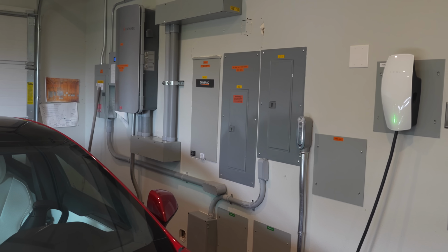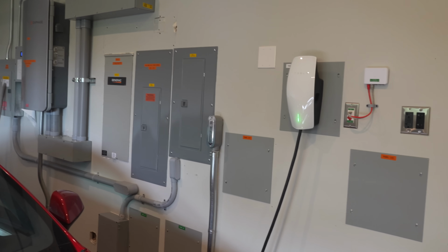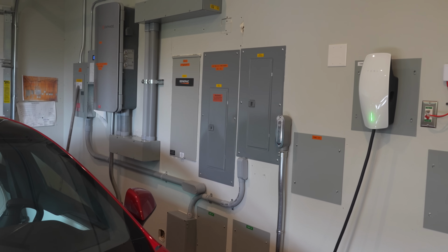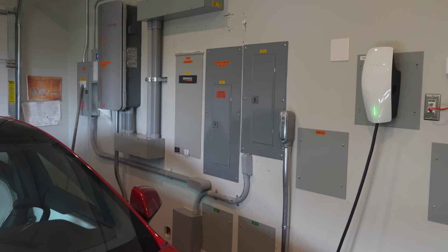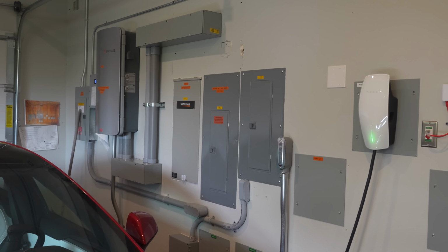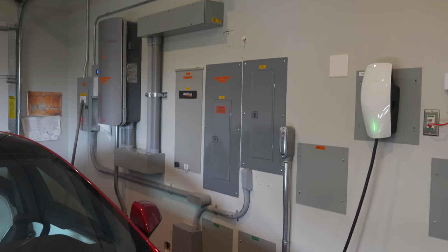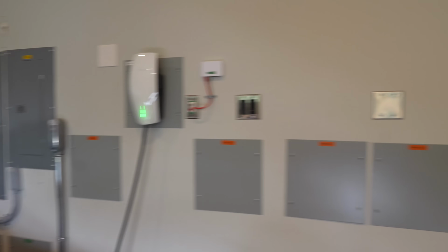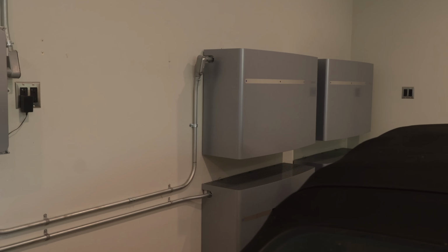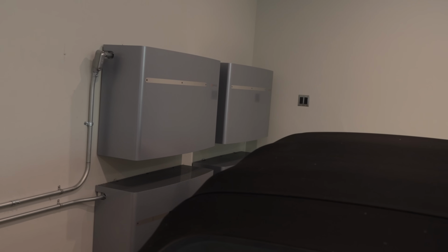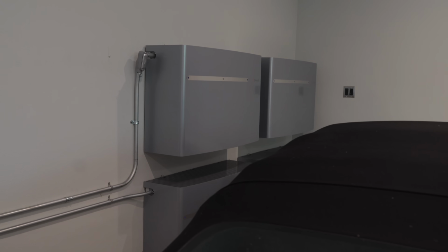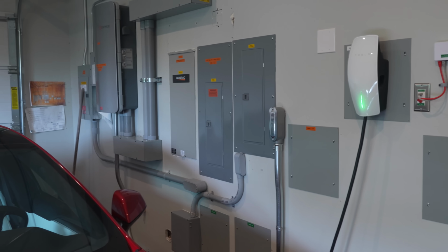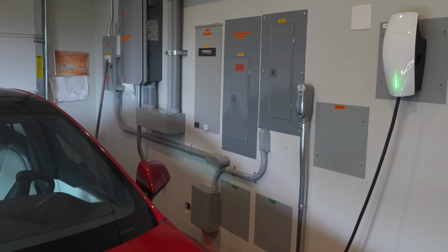And the idea is that if you lose main power, the batteries kick in and will generate an internal grid. And that internal grid can, of course, power the house, the server room and all of the other stuff, but also the solar can generate while you're on that internal grid. And so if it's a sunny day out, the solar can push power back into the batteries if it makes more than you're going to be using. And then if the batteries get low and there isn't enough solar, then it will auto fire up a generator to both charge the batteries and provide house power.